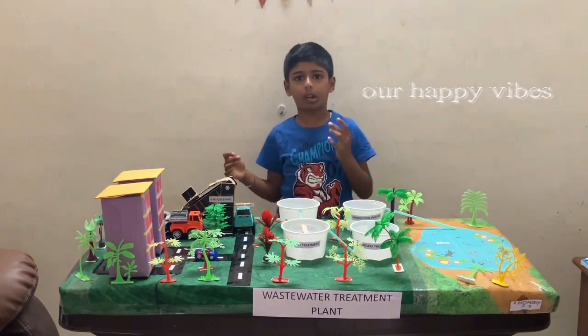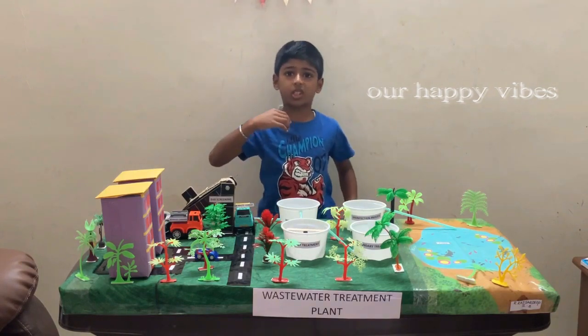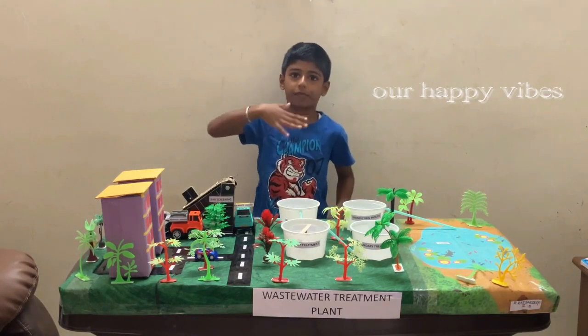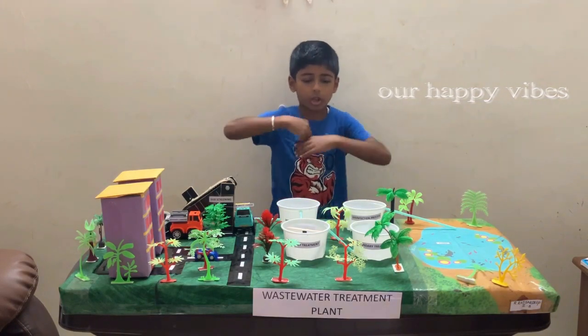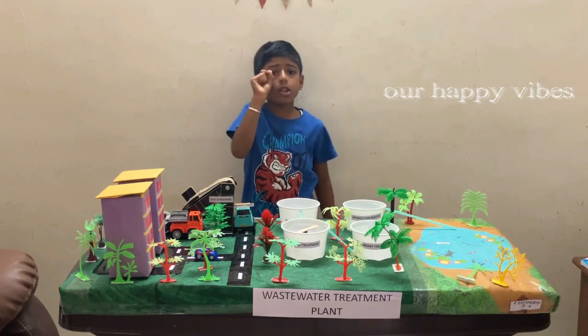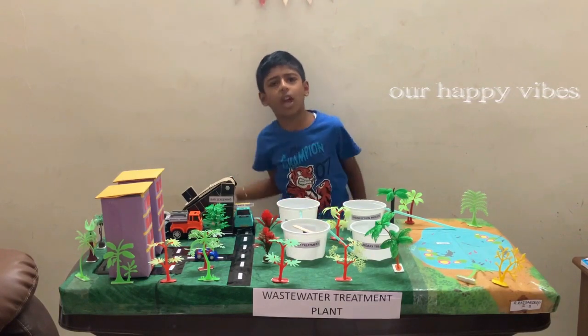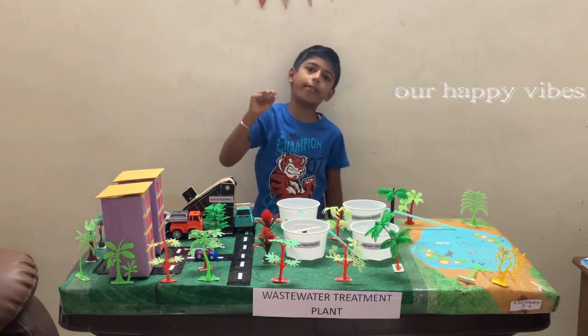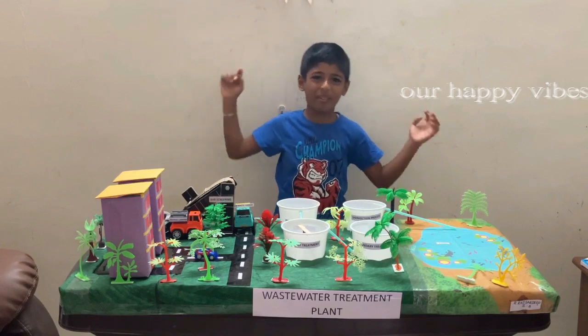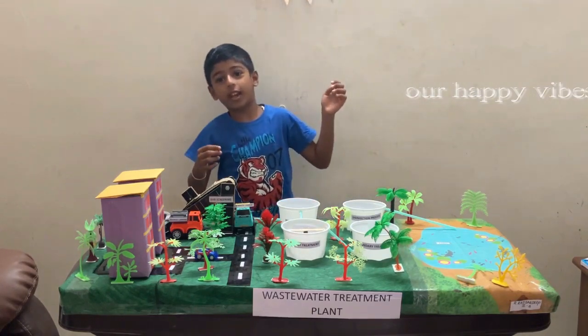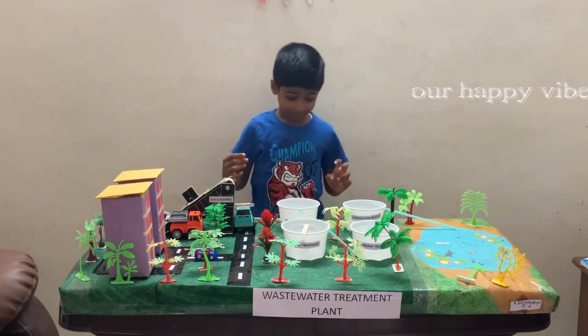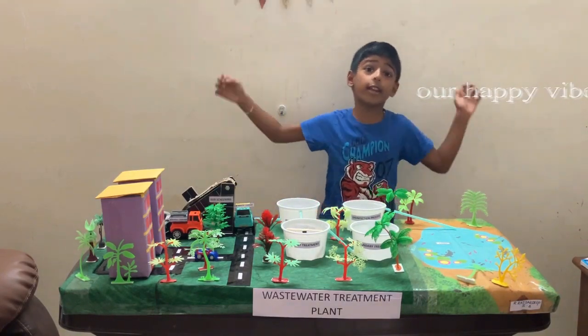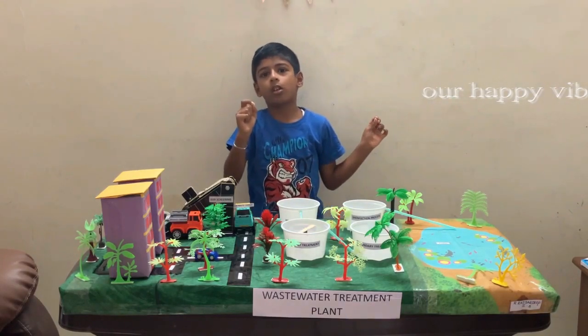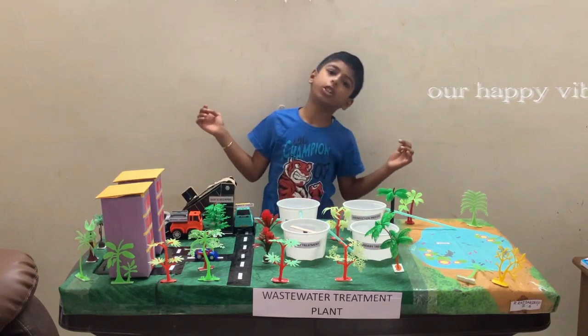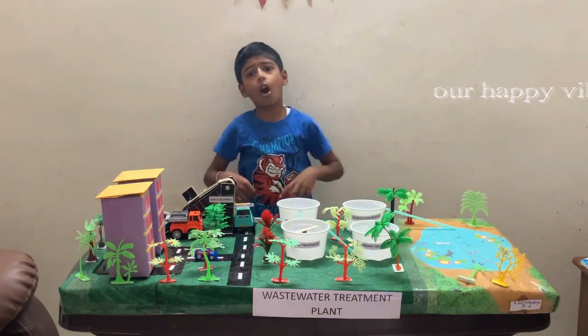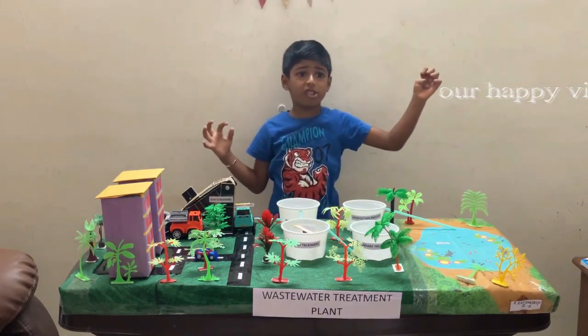Next comes secondary treatment. The main purpose of this chamber is to reduce the biological content of the sewage. This process starts with a large aeration basin. The bottom of this basin contains thousands of tiny air blowers that create bubbles through the water. This allows a bunch of happy little bacteria to eat their favorite food. These bacteria use the oxygen injected by the bubblers in a process called aerobic digestion. Almost 85% of all organic matter is removed at the end of this process.